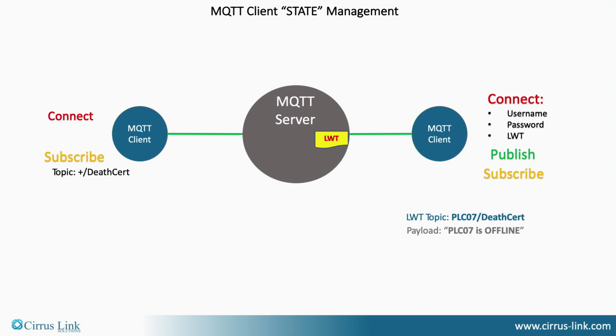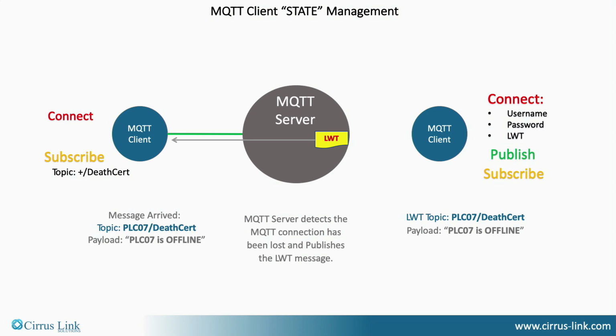Now somebody trips over the Ethernet cable, pulls it out of the switch, and that network disappears. At that moment, the MQTT server detects that we've lost that client out in the field, and it publishes the last will and testament on behalf of that client that's no longer there. This is really the key premise of MQTT and the efficiencies you can get - you get continuous session awareness, but it doesn't cost you bandwidth to keep that up.